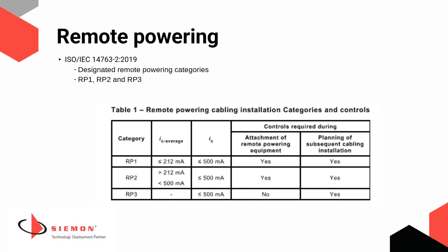For balanced cabling, in accordance with the ISO IEC 11801 series, remote powering equipment shall not supply more than 500 milliamps per conductor, and the installations shall be designed and designated in one of the following categories. Category RP1, attachment of the remote powering equipment at a distributor is controlled such that the average current for all conductors served by the distributor is not greater than 212 milliamps.